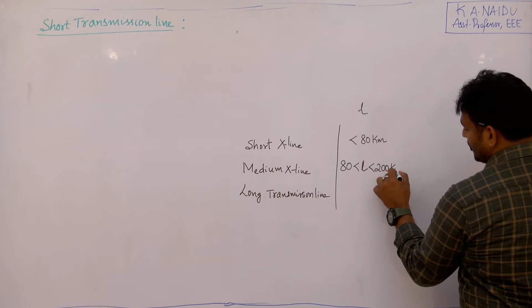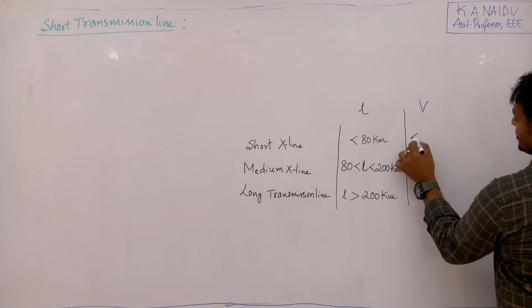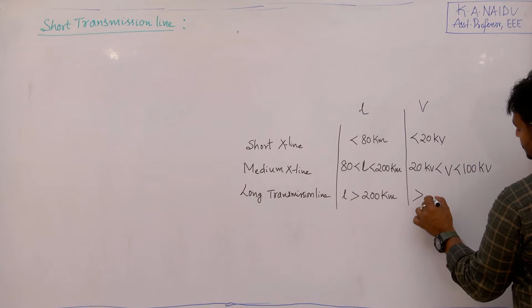So short transmission line means the length of the transmission line is less than 80 kilometers. Medium transmission line, the length is between 80 to 200 kilometers. And for long transmission line, the length is greater than 200 kilometers, and the operating voltages are, for a short transmission line it is less than 20 kilovolts, and for medium transmission line it is between 20 kilovolts to 100 kilovolts, and for long transmission line it is greater than 100 kilovolts.